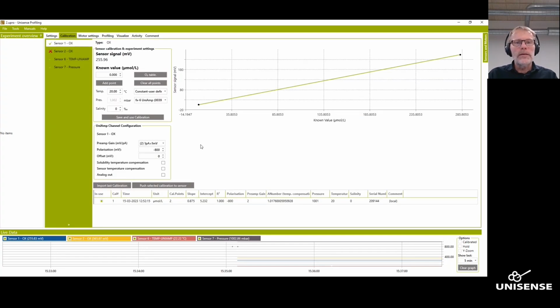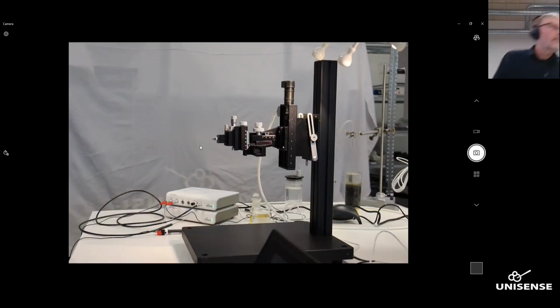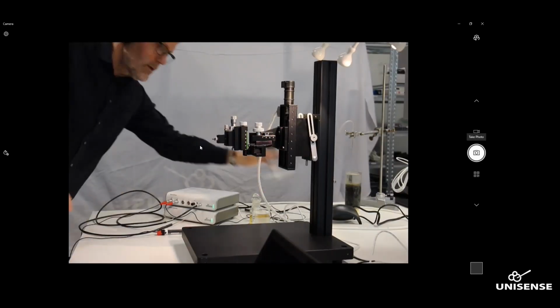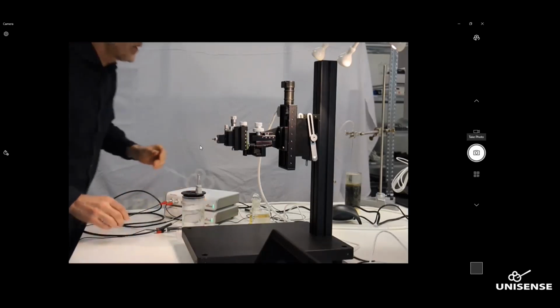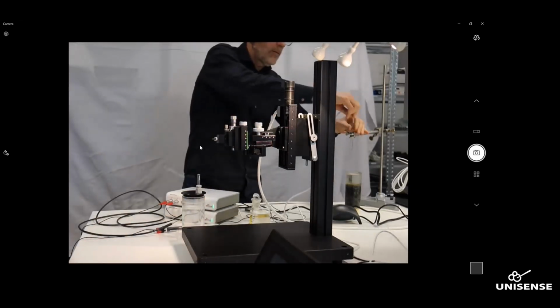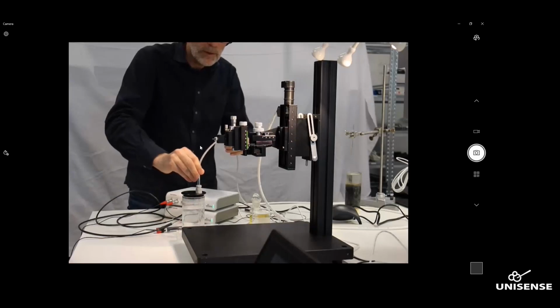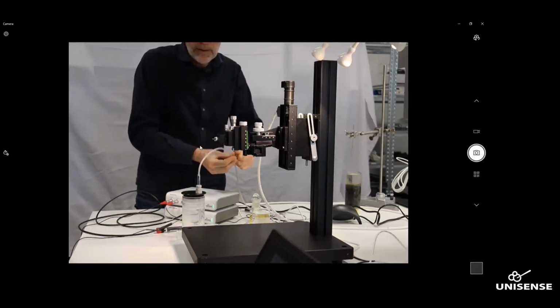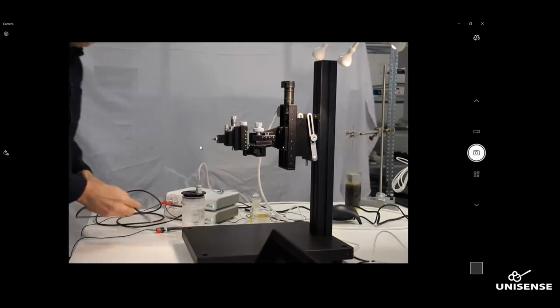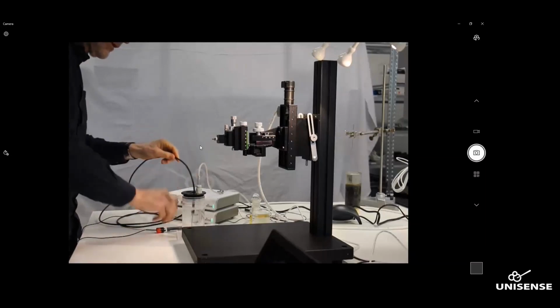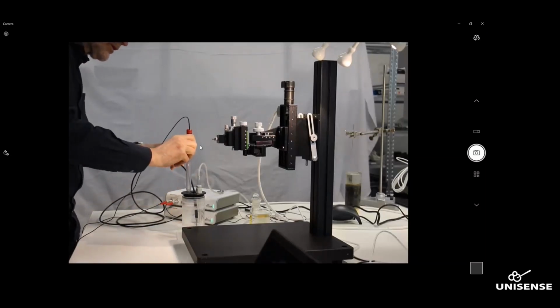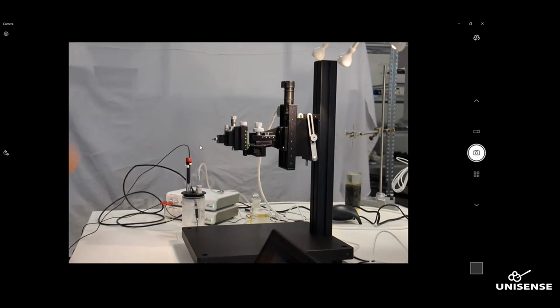Okay, going back to calibration, what I need to do now is make a 2-point calibration of the oxygen sensor. I would like to make a 0 and 1 known concentration. Now for this, I have a calibration chamber here, which has been bubbled with air, but I'll just make sure it is saturated by letting it bubble. Then I'll put my temperature sensor in and the oxygen sensor as well.